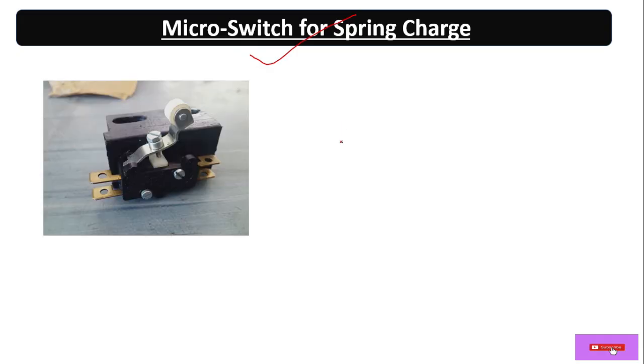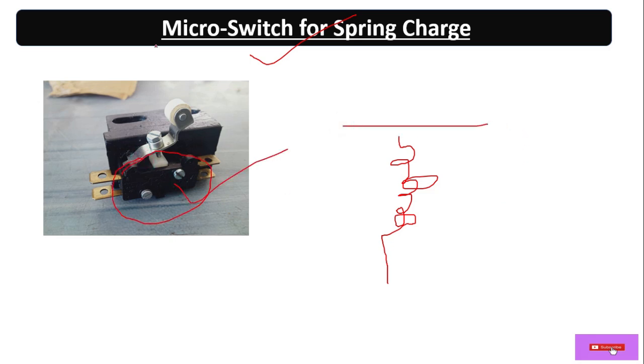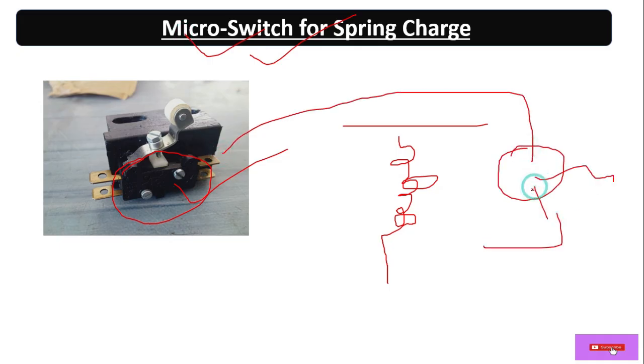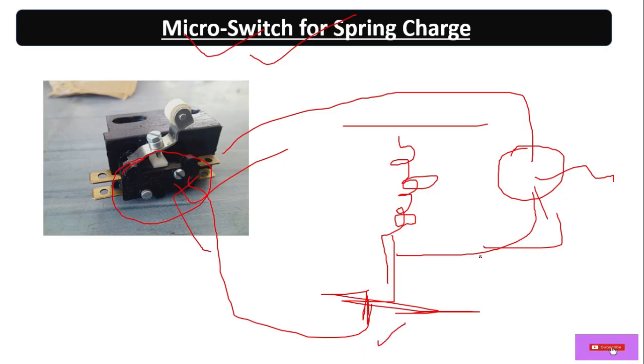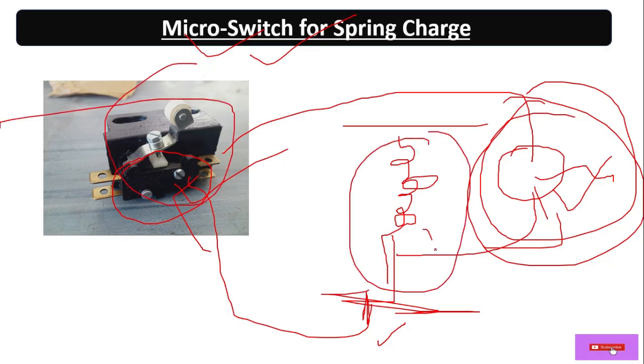The micro switch for spring charge works together with the motor. Suppose the spring is uncharged — in that condition, through the auxiliary contact of this micro switch, the universal motor runs. When the spring reaches the fully charged position, this micro switch will activate and stop the motor. So the motor is integrated with the micro switch based on the spring tension.